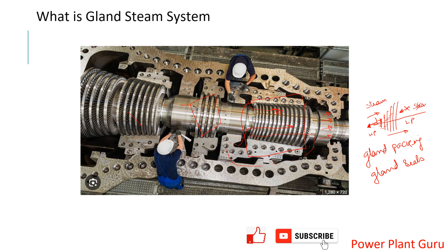Here also there will be some leaks. And at the LP end, if this shaft is going to continue till here, then here also there will be LP side where steam will be escaping. There is a different angle to it on LP side specifically. Imagine on LP side there is a condenser connected or vacuum is there, so air will find its way and come along with this gland packing from atmosphere to inside turbine. Because there is a vacuum, here at LP side there will be air leakages coming in. This is the need and the purpose of gland sealing system.